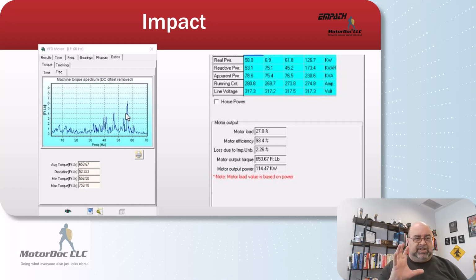One is air gap torque. It's a calculated value of what's going on in the air gap of the machine, and the other is a direct measurement showing the twisting of the shaft. It's a material-related torque. So they're different, and they both provide solid information for different types of things. In any case, one of the nice things, though, in that air gap torque, that allows us to take from the kilowatt data and determine what the actual output is, and the difference between these, that's my losses in the machine. Now, we've seen a couple of companies running around again, marketing bullshit and hype.